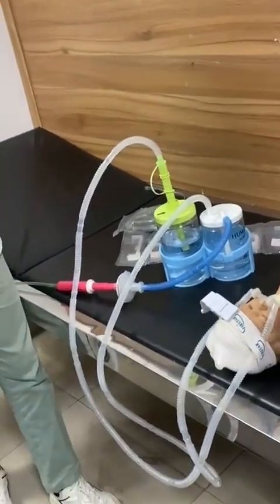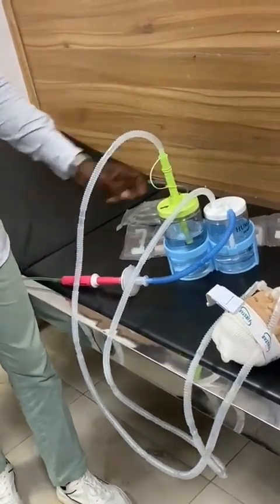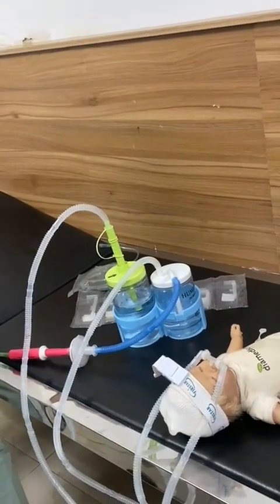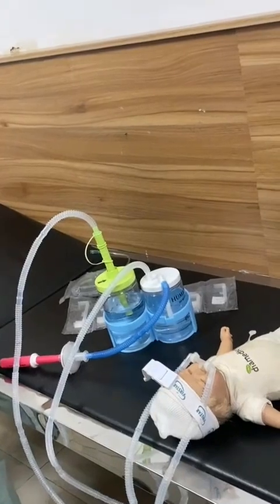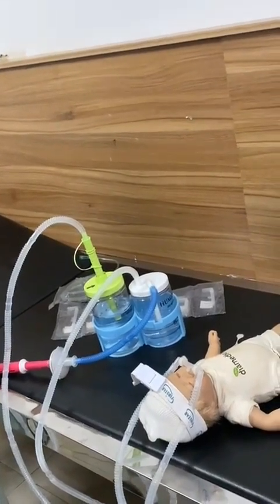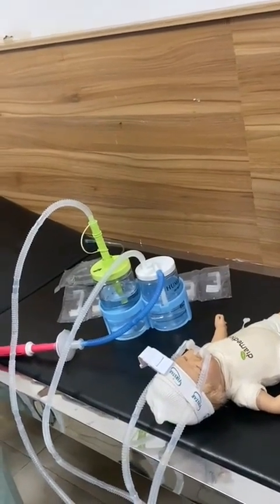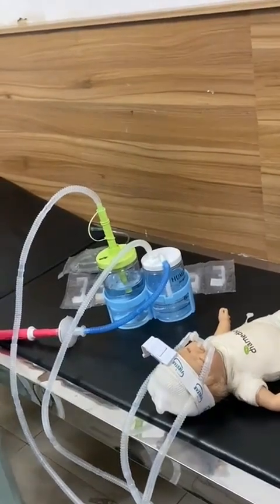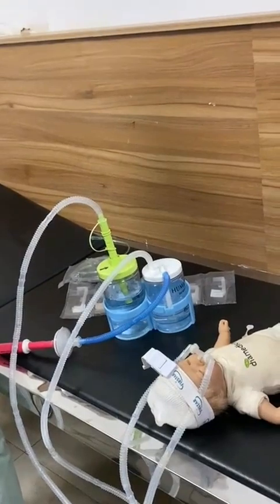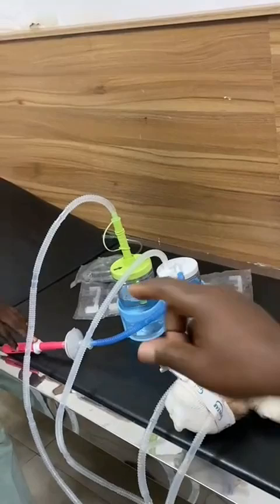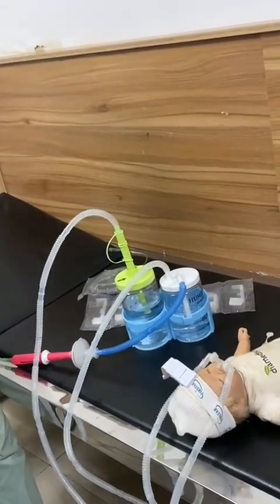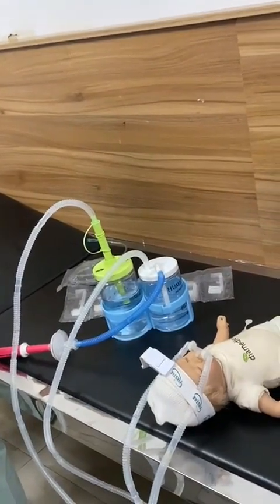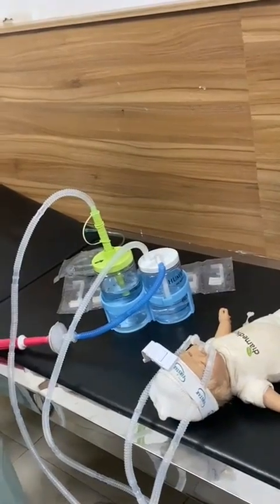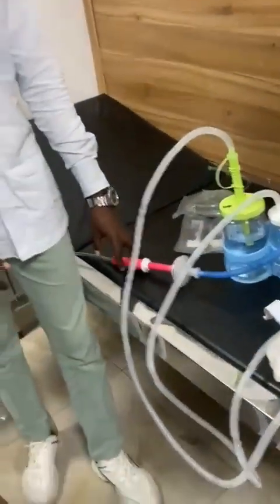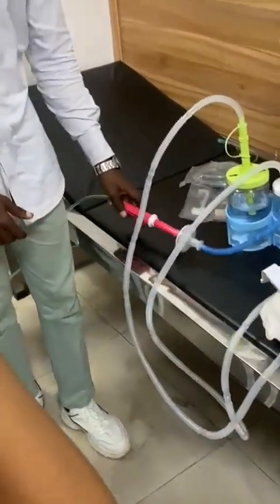By the time you adjust your centimeters of pressure and it's all the way as low as 5, then the baby doesn't need to be on CPAP again. So most times you start at 7.5 or 8, go back to 6, and by the time you get to 5, the baby doesn't need it anymore. So you're still able to maintain the integrity of the system and still have your pressure system. Do you understand? Now, even if you take the oxygen flow rate to 20, what gets to the baby is determined by what you set on the blender. So that no longer becomes a problem. You can take it as high as possible to allow you to build the pressure, but what gets to the baby is determined by the blender.